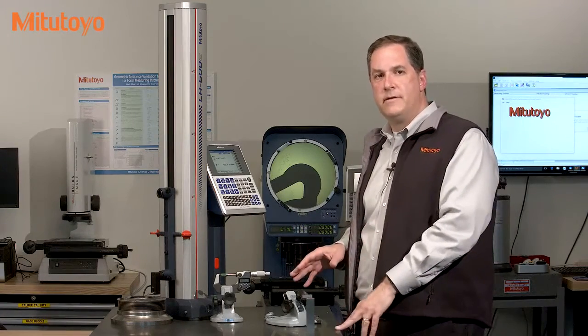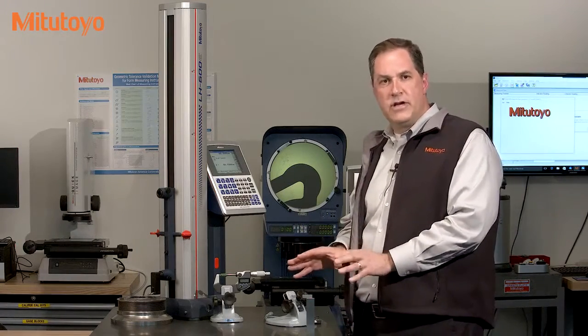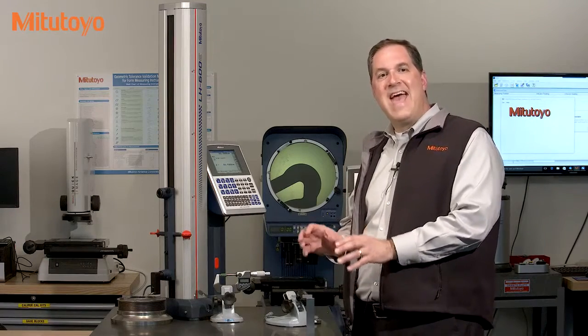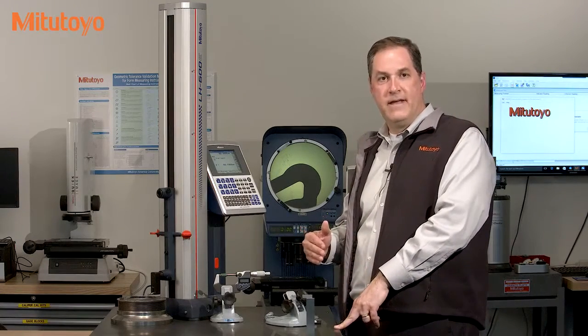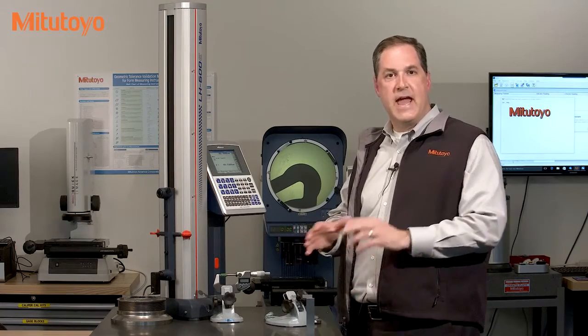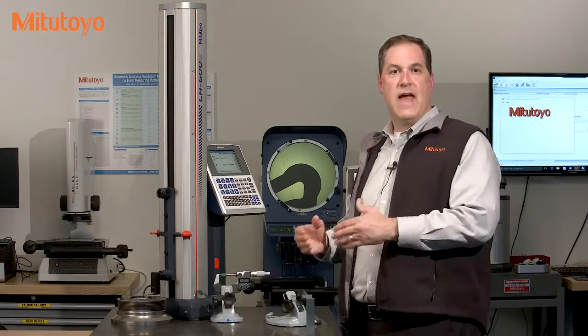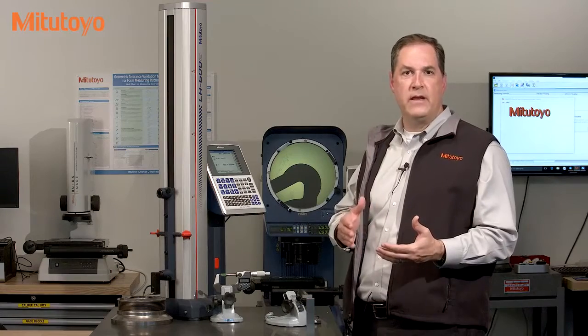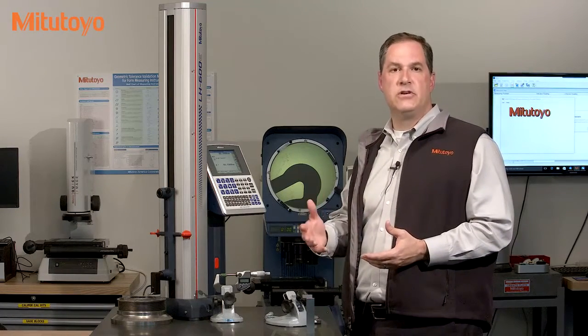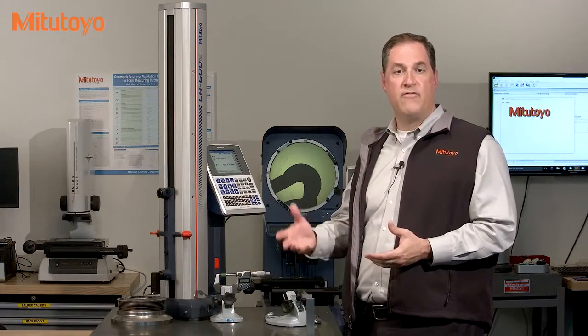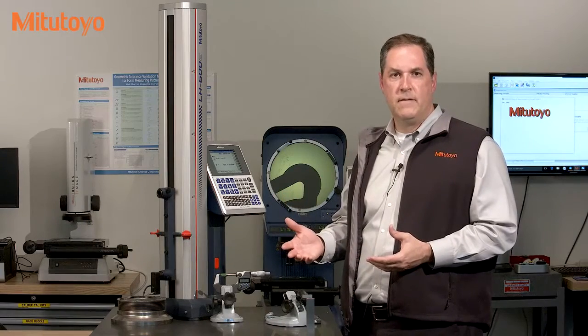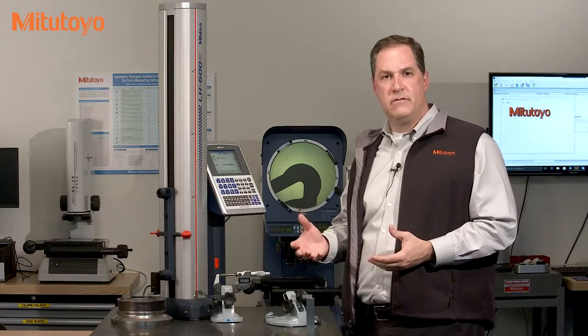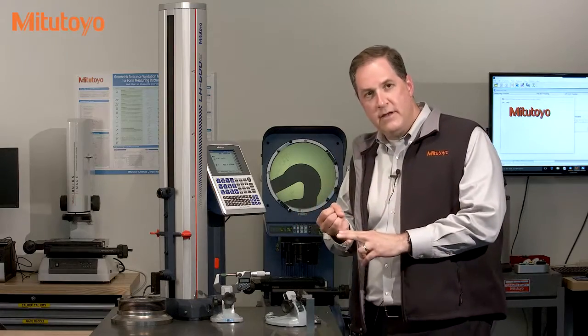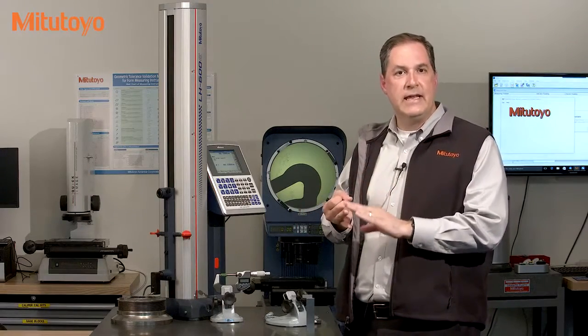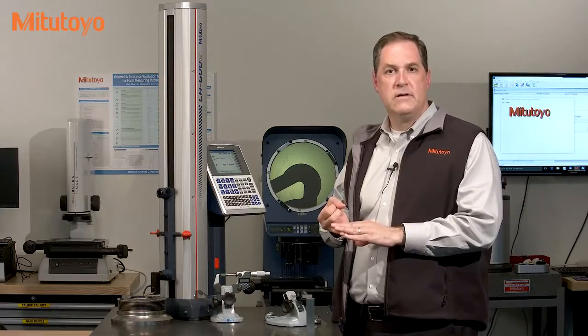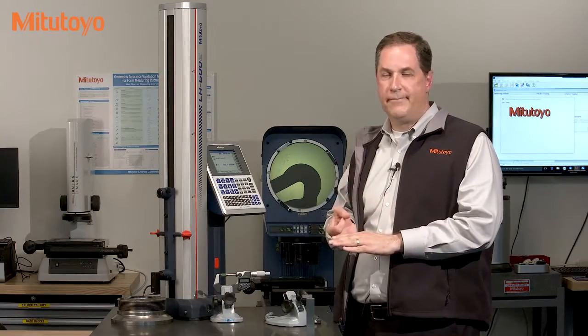Coming back to the calibration. After any cleaning or adjustments are done, the as-left accuracy data is then collected. The same accuracy tests used for the as-found condition are then repeated to determine the final condition of the measuring equipment before it's returned back to service. A complete calibration includes the as-found readings, any necessary cleaning, maintenance, and adjustments, and then the as-left readings.